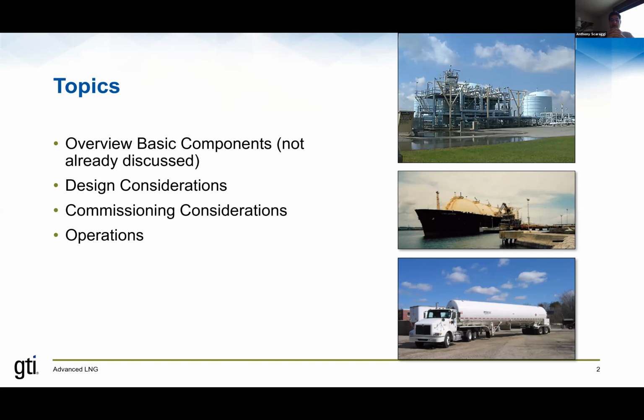It's lighter than water. Natural gas vapors are normally lighter than air, so they rise if released. But keeping in mind, LNG is a cryogenic liquid. When you first release the LNG, the initial vapors you get will be very cold, and those vapors will remain heavier than air until they're warmed up to about minus 160 degrees Fahrenheit. At that point, they'll be neutrally buoyant, so any warmer than that, they'll rise. They'll dissipate into the atmosphere.